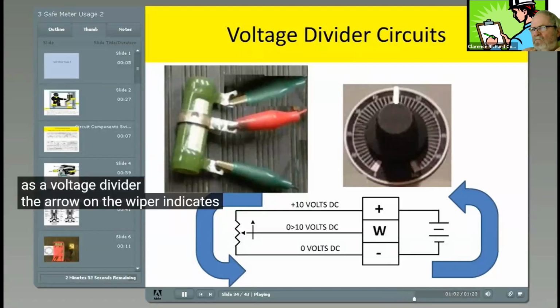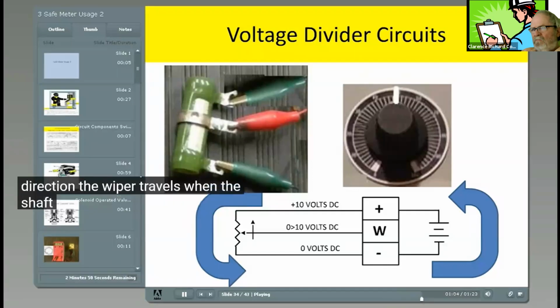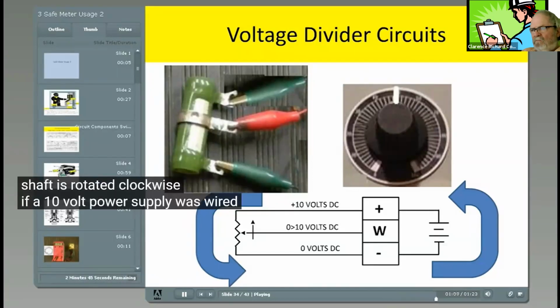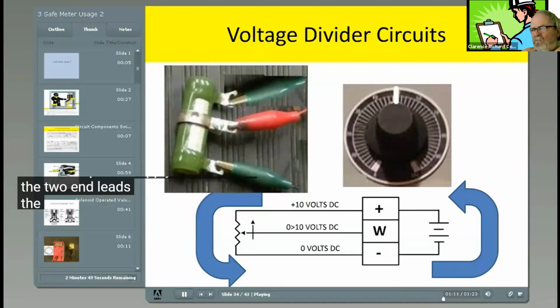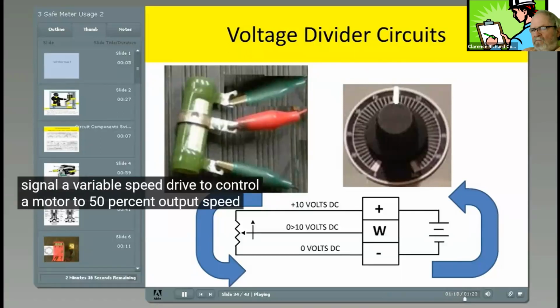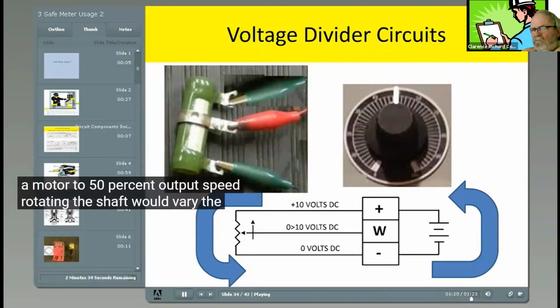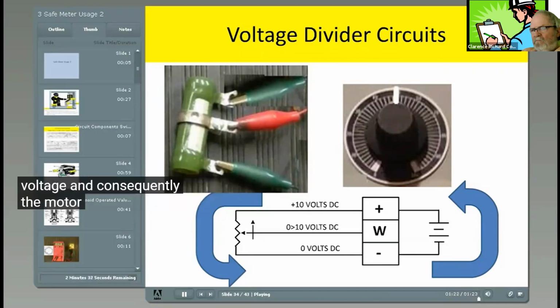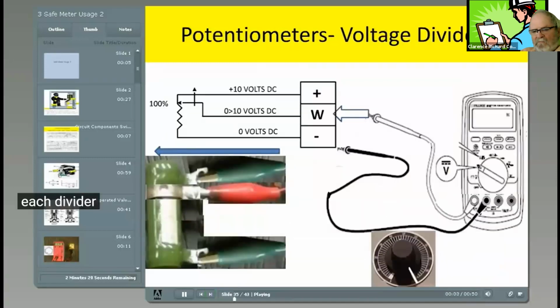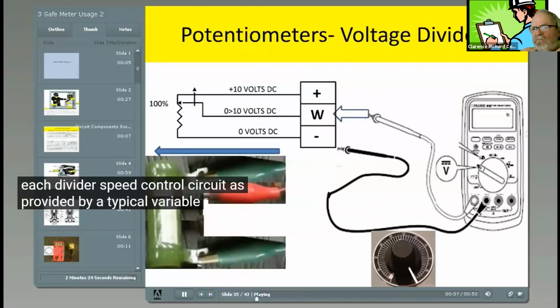The arrow on the wiper indicates the direction the wiper travels when the shaft is rotated clockwise. If a 10-volt power supply was wired to the two end leads, the wiper voltage of 5 volts could signal a variable speed drive to control a motor to 50% output speed. Rotating the shaft would vary the voltage and consequently the motor speed. Divider speed control circuit, as provided by a typical variable speed drive control terminal board.